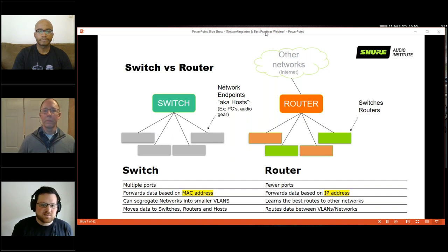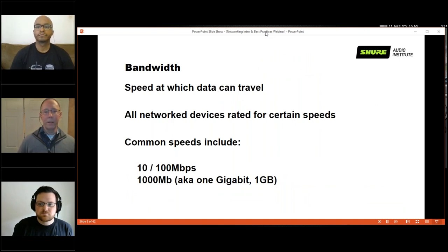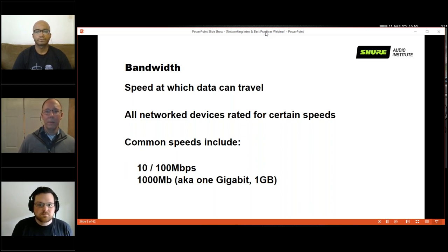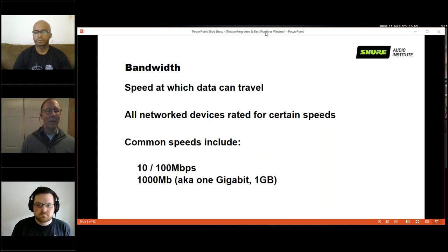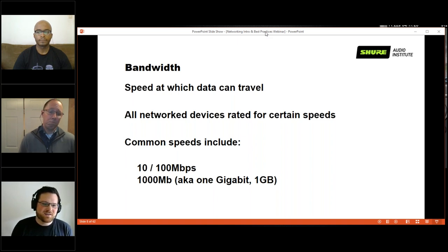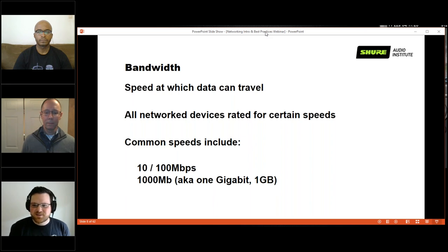For control networks, 100 Mbps is probably fine per spec, but for Dante networks we always specify gigabit — it can technically work at lower channel counts on 100 Mbps, but we never want that to become a problem as the network scales up. Bandwidth is a form of quality of service in a way, which we'll get into later.